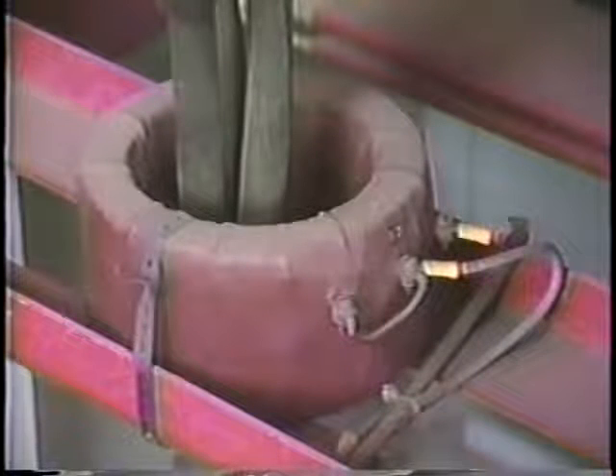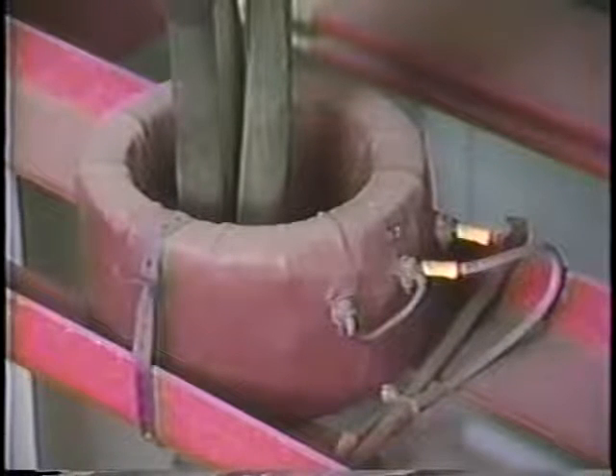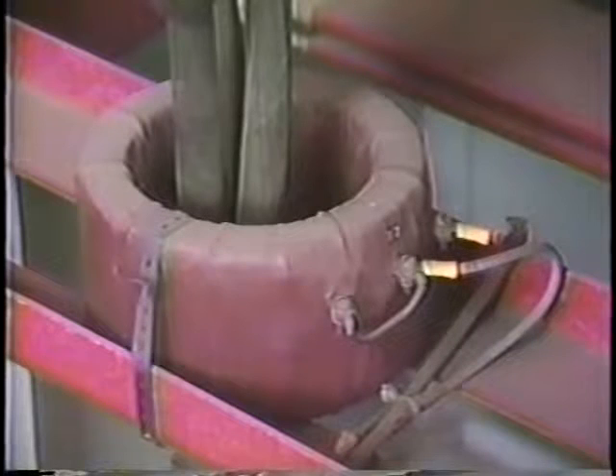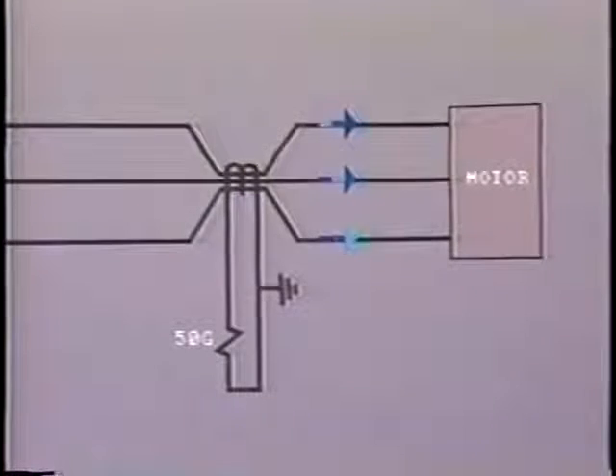The best way to detect this is through the use of a toroidal CT, which is connected to an instantaneous relay. All three supply leads to the motor pass through the window of the transformer. As long as the three currents are balanced, the value of CT secondary current is close to zero.